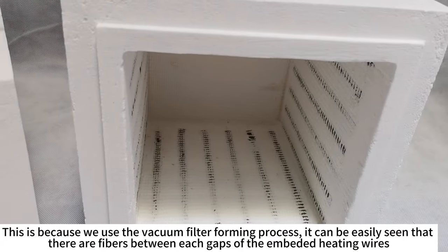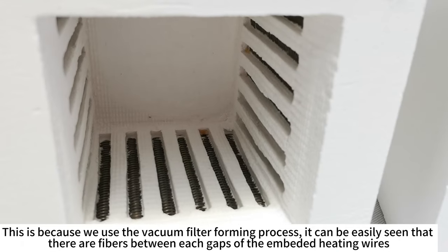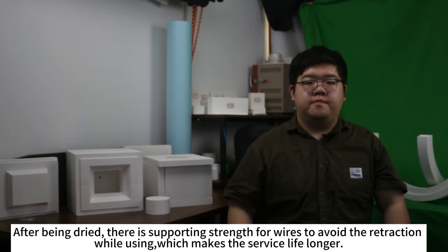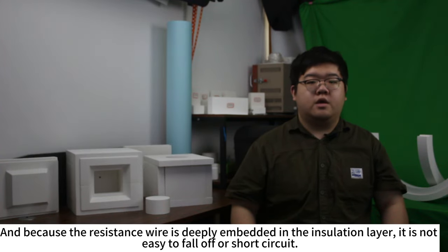This is because we use the vacuum filter forming process. It can be easily seen that there are fibers between the edge gaps of the embedded heating wires. After being dried, there is a supporting strength for the wires to avoid retraction during use, which makes the service life longer. And because the resistance wire is deeply embedded in the insulation layer, it is not easy to fall off or short circuit.